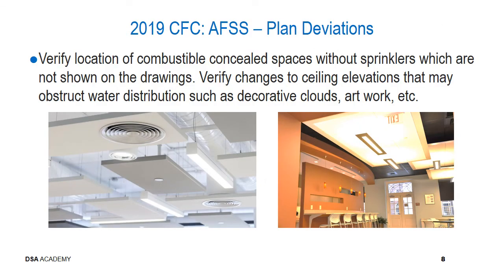Verify the location of combustible concealed spaces where sprinklers are not installed, which are not shown on the drawings. Verify changes to ceiling elevations that may obstruct the water distribution, such as decorative clouds, artwork, or other suspended items. Cloud ceilings are addressed in NFPA 13, Section 8.15.24. The location, height, and cloud layout must be per the DSA approved drawings. Any deviations must be submitted to DSA for review and approval through the CCD process.